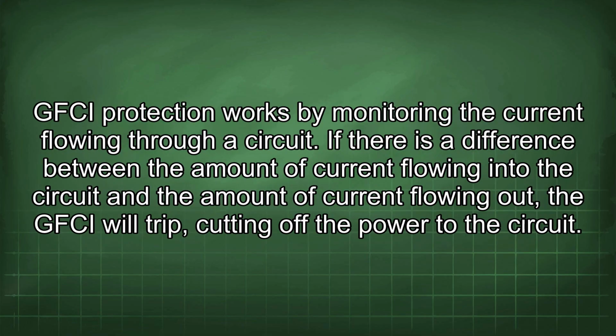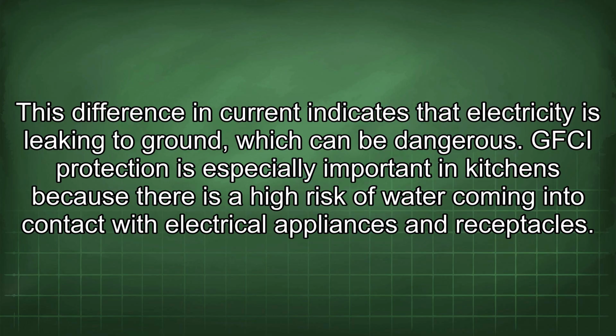GFCI protection works by monitoring the current flowing through a circuit. If there is a difference between the amount of current flowing into the circuit and the amount of current flowing out, the GFCI will trip, cutting off the power to the circuit. This difference in current indicates that electricity is leaking to ground, which can be dangerous.